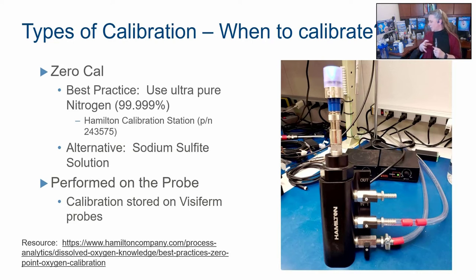What that solution does is it basically destroys all the oxygen in the solution. So then you can put your probe into that solution and suspend it. You don't want it resting, but you suspend it, and it's a zero oxygen solution. Super simple. Okay. When you do that, again in our software, you say, that's a zero cal. And as long as the temperature's stable, it goes, yes, it is. And it writes that value of the phase shift for that into the probe. That's zero cal. Both of those are completely legitimate.